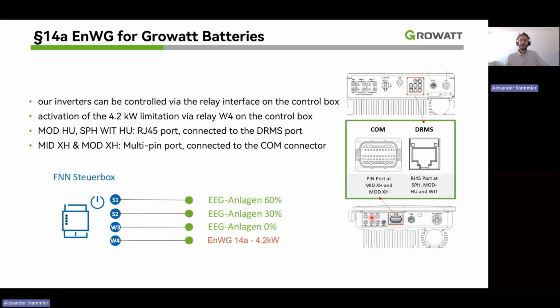the PV system. So with the HU system, we have the DRMS contact. Also with other systems from us like the SPH, all of them who have a DRMS contact, we use this one for the export limitation controlled by the grid provider, and for the import limitation controlled by the grid provider. So the export is EEG paragraph 9 or so, which says that to a certain time the grid provider needs to be able to shut down export up to 0%, 30%, or 60%.